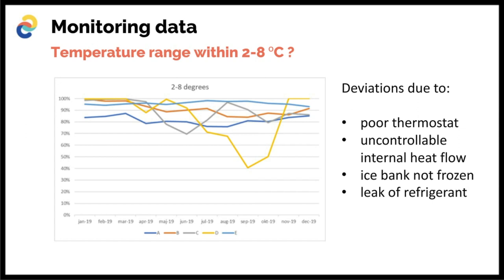These problems have been investigated, and mostly they have been due to poor thermostat function, uncontrollable internal heat flows from poor design, or that the ice bank has not been fully frozen. If that happens, we do not have the full thermal capacity, which means if you have some cloudy days, the vaccine will heat up, which is not optimal.